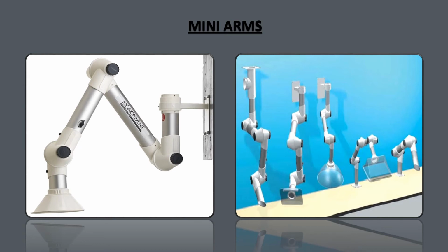We can also do what we call the LFK kit, or local filter kit. Let's say you have a soldering type application with a small soldering bench, and maybe you don't want to tie into your central fan system. The LFK kit comes with a small adjustable speed fan, a small cartridge collector, and 1 or 2 arms. The cartridge collector fits right underneath the desk or bench, you put your arm or 2 arms on top, and you're able to capture the exhaust, clean it through the cartridge system, and expel that air right back into the work environment.